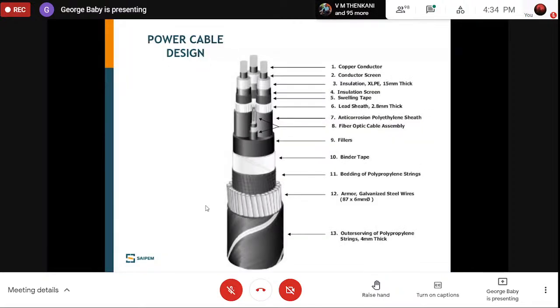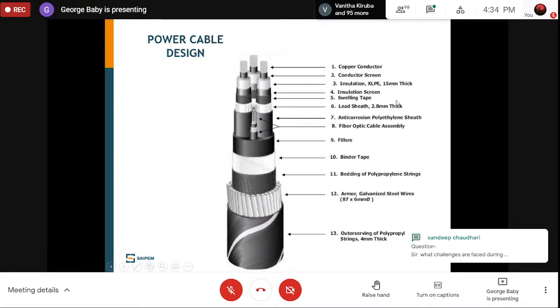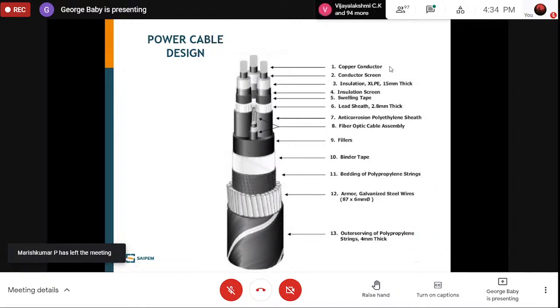And here is a standard design of a power cable. This is taken from an 11 kV cable. As you know, the conductor will always be copper, and there will be a conductor screen. Then there will be XLPE insulation, and on top of it there will be a lead sheath, and on top of that there will be anti-corrosion. This is required because, as we discussed before, we are laying this cable for a lifespan of 20 years. So these anti-corrosion sheaths are required to protect the cable from corrosion for a long time.